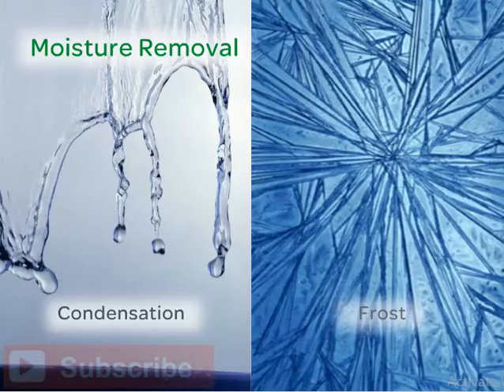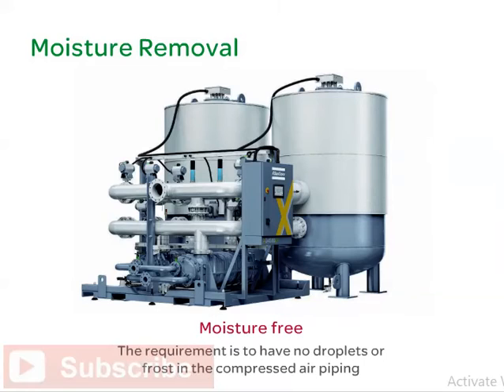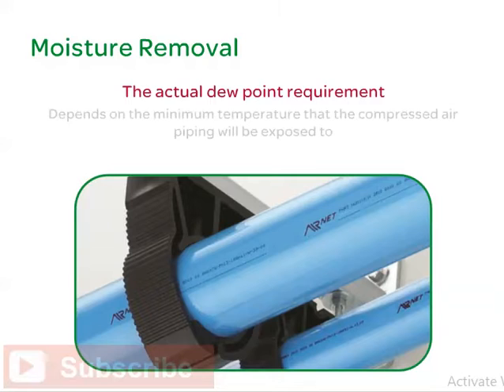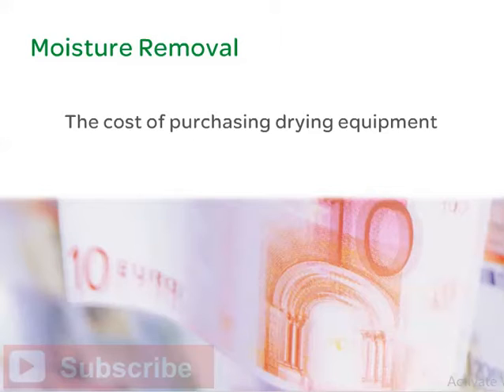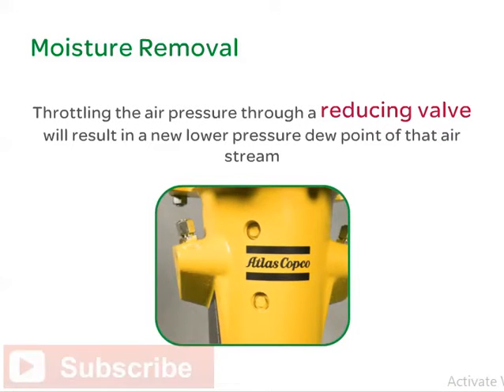Typically, compressed air must be dried because the equipment that relies on compressed air needs to be moisture-free. Moisture-free can have many definitions, but generally the actual requirement is to have no droplets or frost in the compressed air piping. The actual dew point requirement normally depends on the minimum temperature that the compressed air piping will be exposed to, but there can be process requirements for dry air too. The level of dryness required has a direct impact on the cost of purchasing drying equipment and the cost of drying the air. Throttling the air pressure through a reducing valve will result in a new, lower pressure dew point of that airstream.